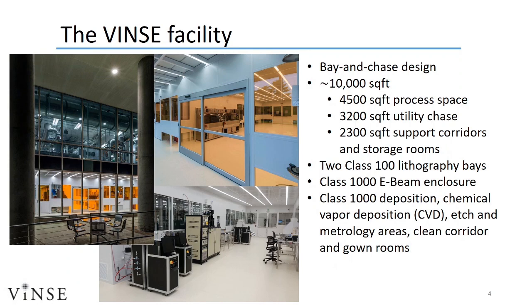Most of our clean room is class 1000, including our deposition and etch bays, as well as the gowning room and main corridor. We have two lithography bays that are class 100, which are enclosed behind a sliding door and also illuminated with amber light to filter UV wavelengths. While it is also illuminated in amber light, our e-beam enclosure is class 1000. It is isolated through doors to filter acoustic and vibrational interference and preserve resolution on the electron microscope housed inside.